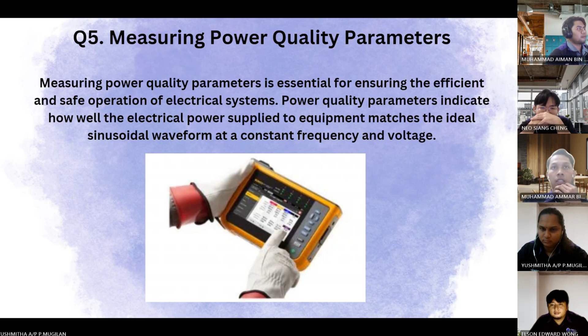So the first point is to list and describe the instrumentation used in PQ measurement, for example, power analyzers and harmonic meters in Malaysian facilities. So first of all is the power quality analyzer. Power quality analyzers in Malaysia are widely used by TNB and industry, measuring voltage, current, harmonics, power factor, sags, swells, and transients. They offer simultaneous measurement, real-time logging, historical data, and comply with IEC 61000-4-30 standards. Harmonic meters in Malaysia are used in facilities with non-linear loads, such as data centers and manufacturing plants, to measure harmonic distortion in voltage and current, expressed as total harmonic distortion, THD.